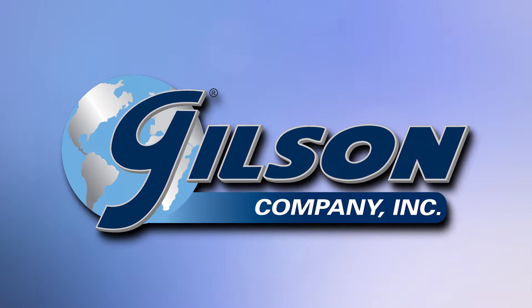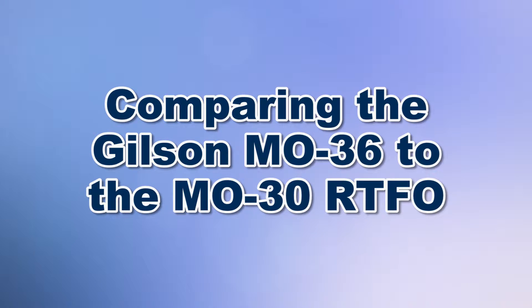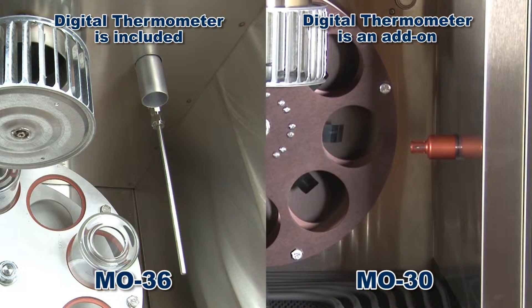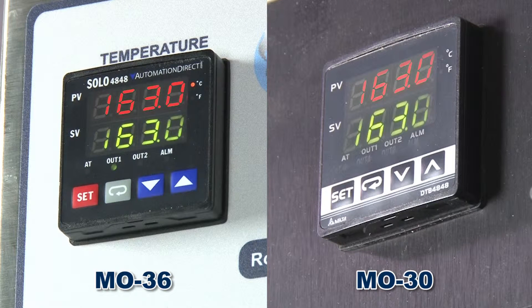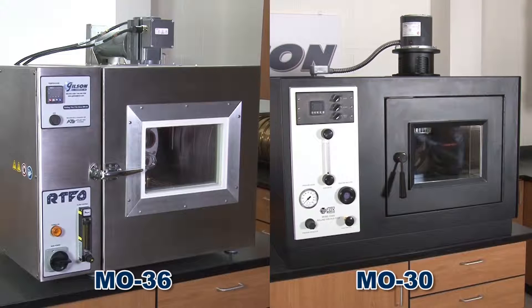Let's compare the Gilson MO-36 and the Gilson MO-30 rolling thin film ovens. Both feature a built-in NIST traceable platinum resistance temperature detector, a solid-state display for simultaneous viewing of actual temperature and set point temperature, and both units prevent the oven from overheating in the event of a controller failure.